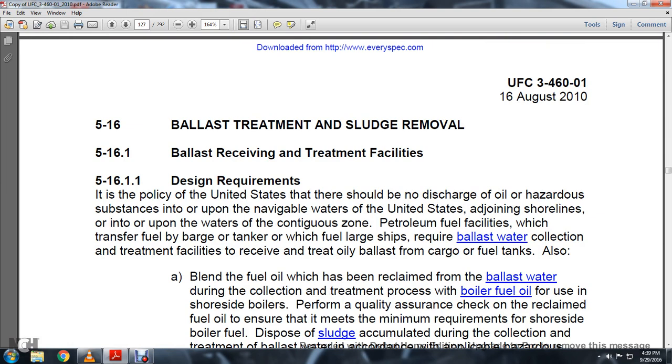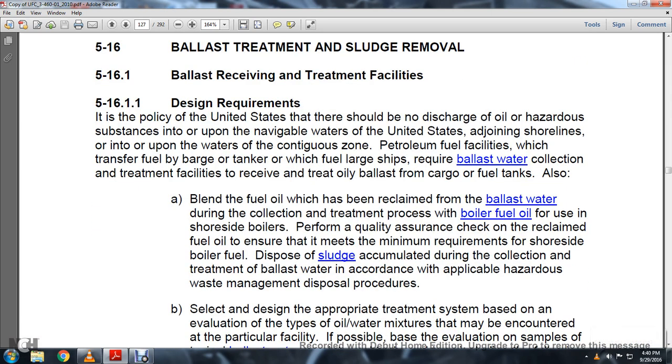Section 5.16 Ballast Treatment and Sludge Removal. Section 5.16.1 Ballast Receiving, Transport, and Treatment Facility — Design Requirements: It is the policy of the United States that there shall be no discharge of oil or hazardous substances into navigable waters of the United States, adjoining shorelines, or contiguous zones. Petroleum fuel facilities, which transfer fuel by barge or tanker or which fuel large ships should require ballast water collection and treatment facilities to receive oily ballast from the cargo fuel tanks. Blend the fuel reclaimed from ballast water during collection and treatment with boiler fuel oil for shoreside reuse, performing a quality assurance check to ensure the reclaimed fuel oil meets minimum requirements for shoreside boiler fuel. Dispose of sludge accumulated during ballast water treatment in accordance with applicable hazardous waste management and disposal procedures.